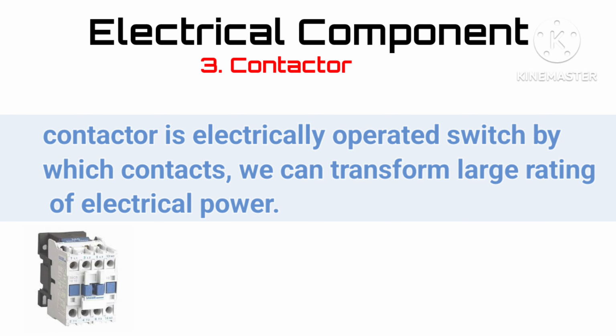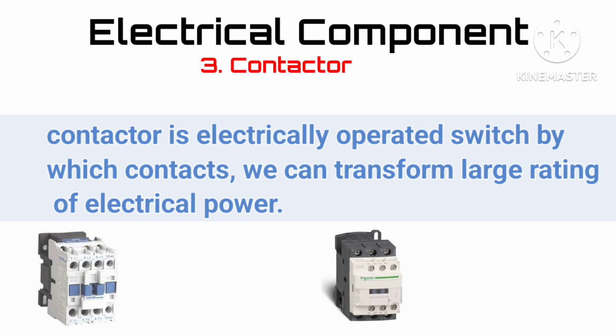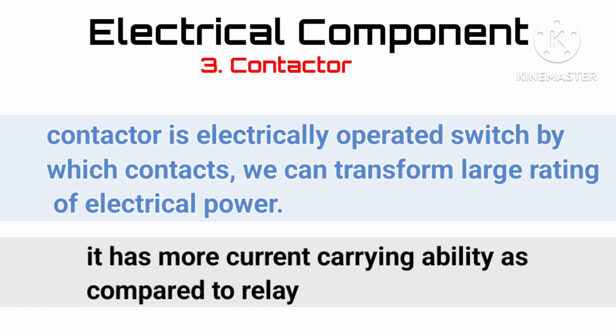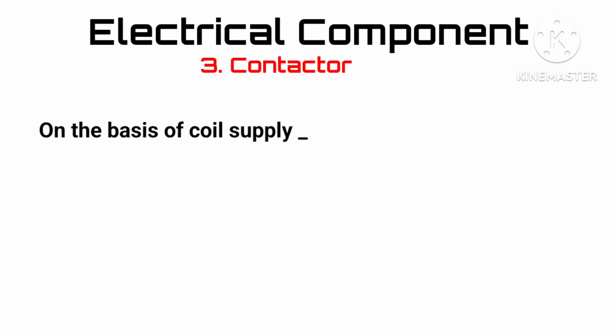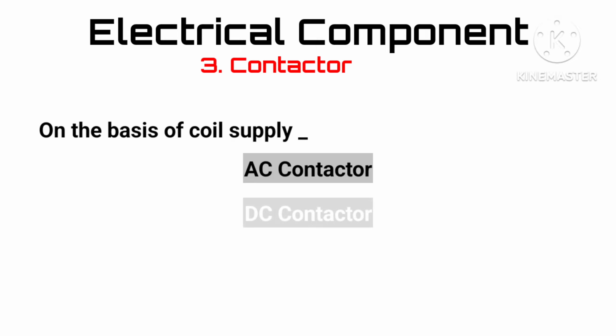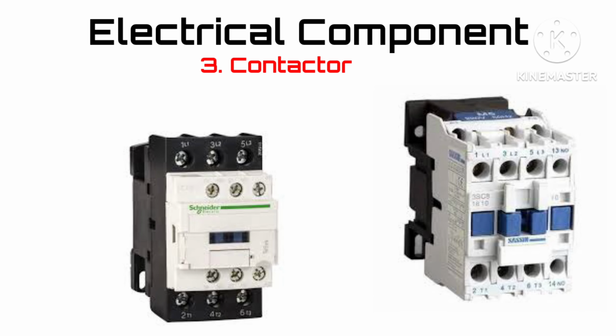An electrical contactor is an electrically operated switch by which a large amount of electrical power is switched. A contactor is similar to a relay but it has a higher current rating. On the basis of electromagnetic coil supply, there are two types of electrical contactor: one AC operated, second DC operated, but the operation and mechanism are the same.